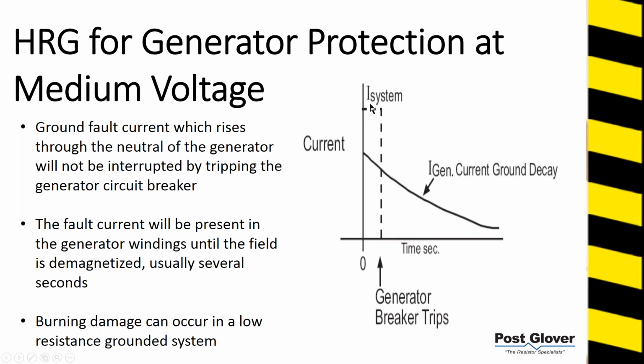Essentially, you could potentially have a situation where, I think I've gone over this in our hybrid grounding webinar before, you trip here, but your generator is still winding down, so you have some additional damage that can occur here. If you had a high resistance ground system tied to the generator, you would not have to worry about this additional damage on the generator. So that's kind of the idea of it.